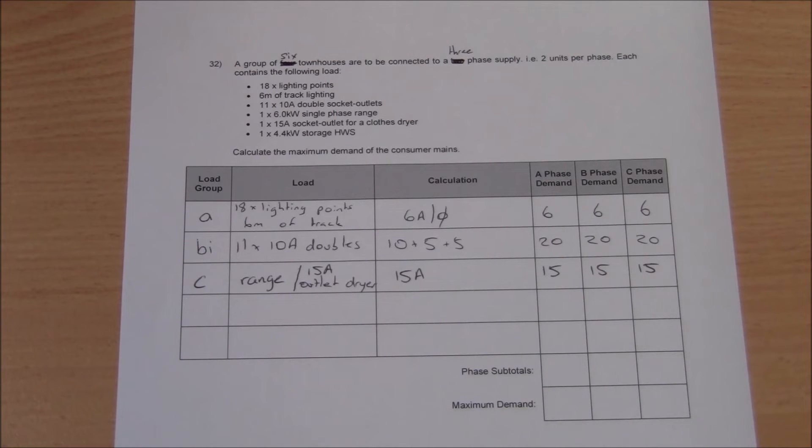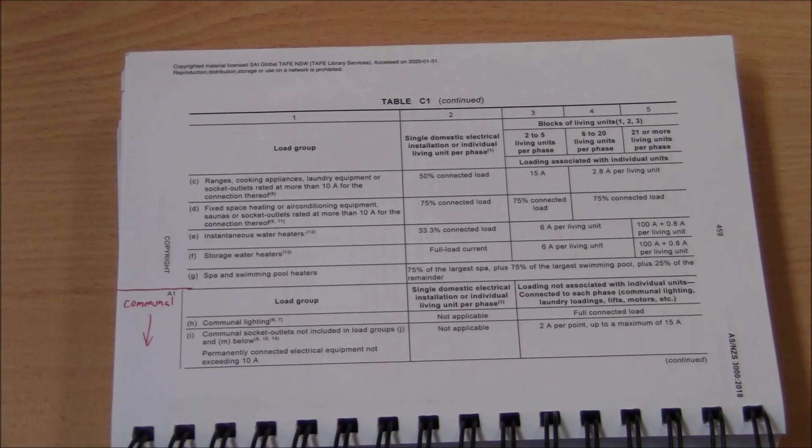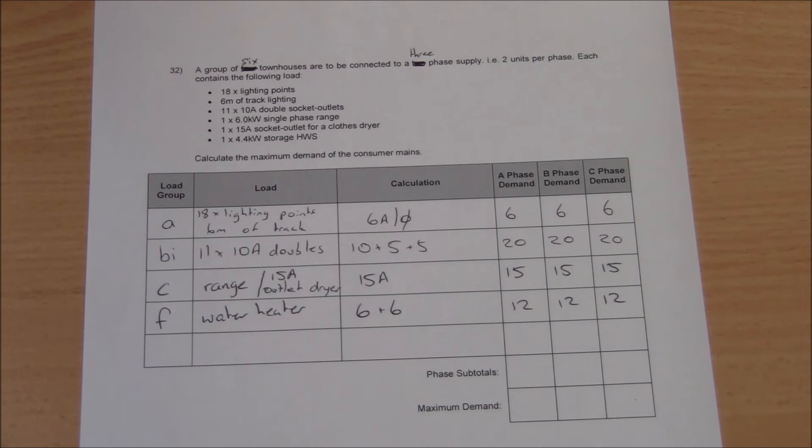Finally, each unit has a 4.4 kilowatt storage water heater. Storage water heaters fall under load group F, and column 3 states we would add a 6 amp per unit per phase contribution. As a result, we will add 12 amps per phase.